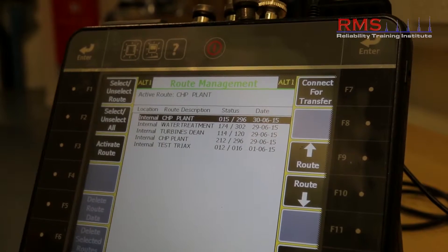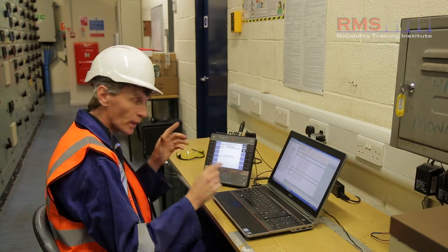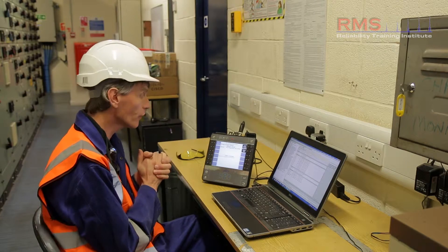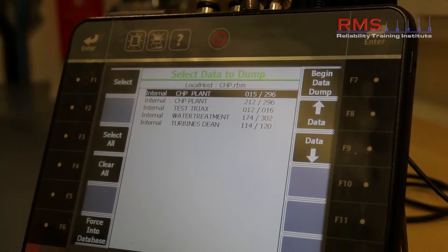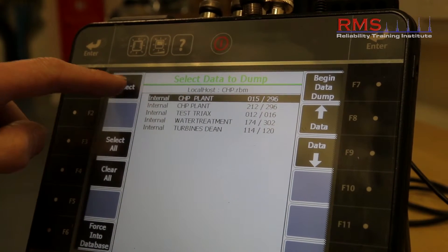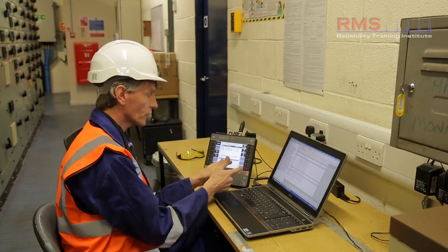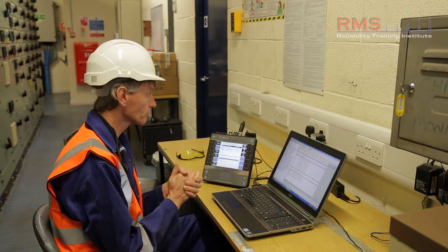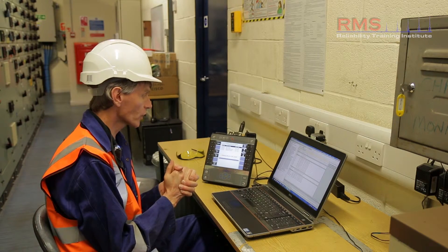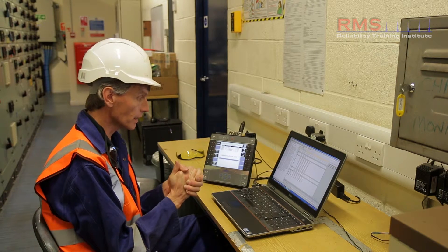I'm going to select the connect for transfer button, which establishes communication between the PC and the analyzer itself, then select dump data from the instrument and choose the CHP plant to begin the data dump. The data is transferred via USB, or it could be wireless or Ethernet, and is now being sent back into the PC where it will be saved and secured.